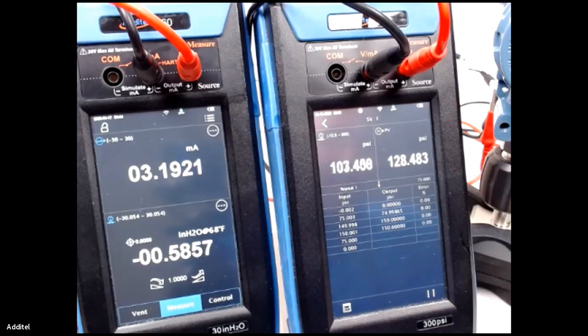Now it's dropping down to the 75. So we literally just did a 7-point cal right there in the time this has been running. And when we get done, we can save this data as found, as left, or both, and record it.